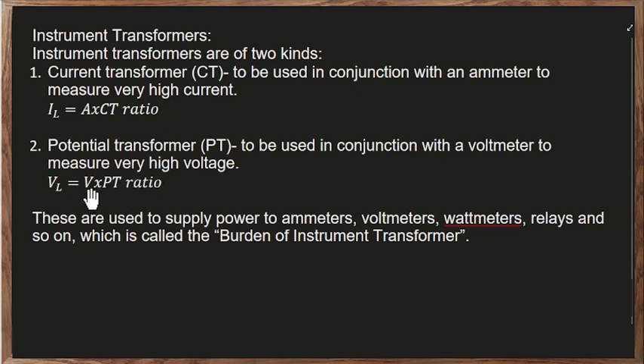If we get the product of the two, magkakaroon tayo ng line voltage, and that is the actual line voltage. So these are used to supply power to ammeters, voltmeters, wattmeters, relays, and so on, which is also called the burden of instrument transformers. So yung mga load ng instrument transformers are usually the instruments, no, ng isang system, which could be an ammeter, pwede rin voltmeter, wattmeter, relays, frequency meter, and so on and so forth.